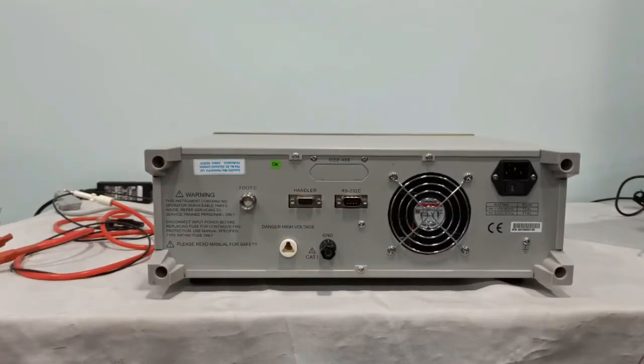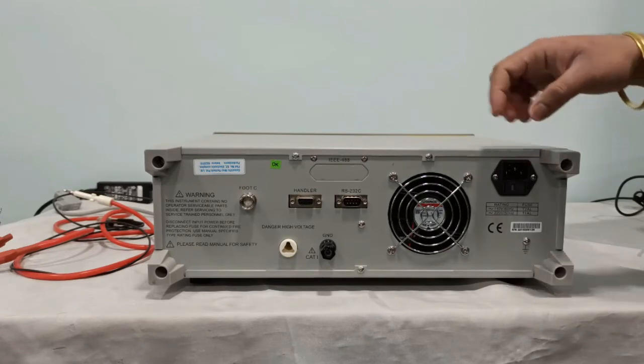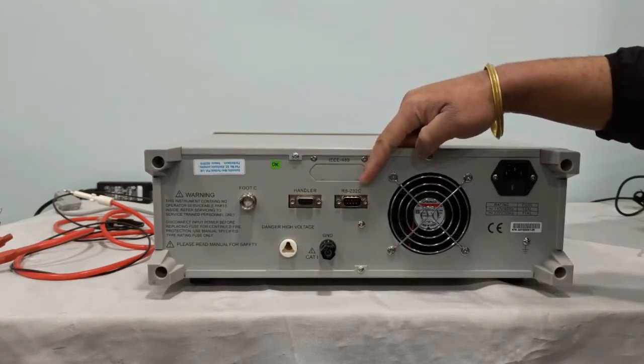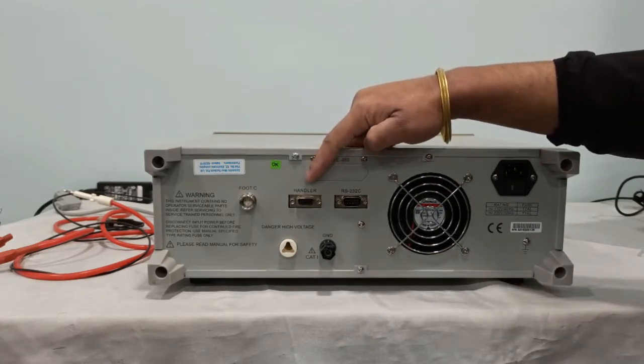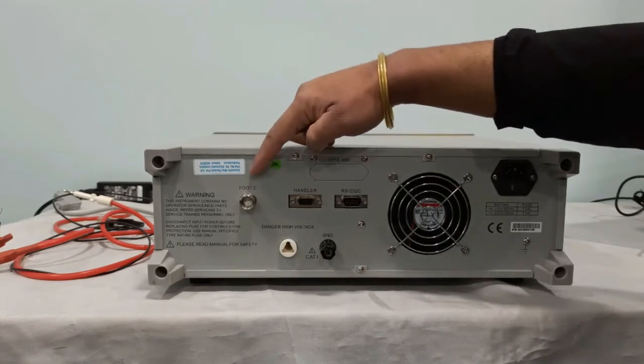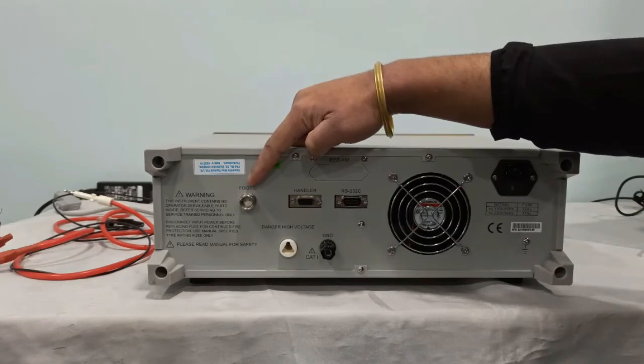Now this is the rear side of the instrument. So this is the mains input, AC input. This is the RS-232 for communicating with PC. This is the handler interface to control the instrument or taking the pass fail output. Now this is the foot switch. This is also for external triggering.